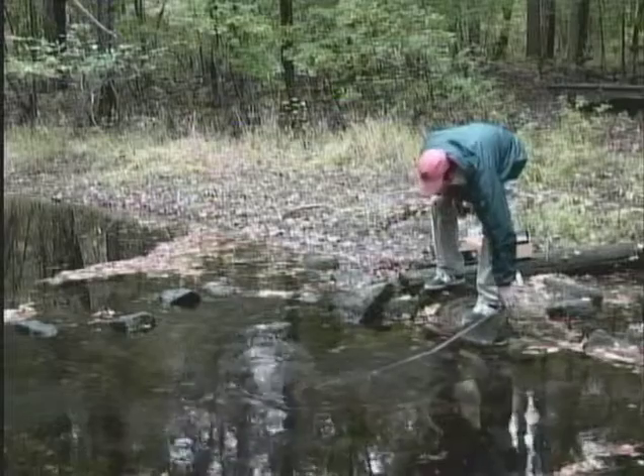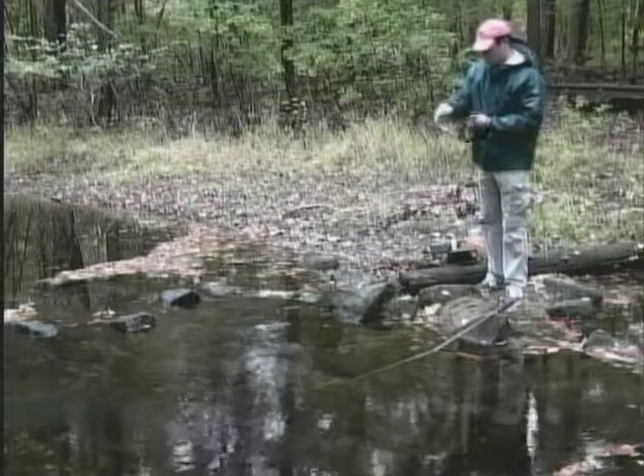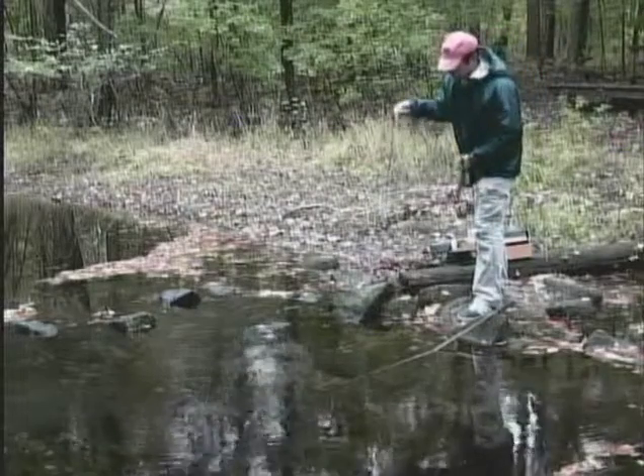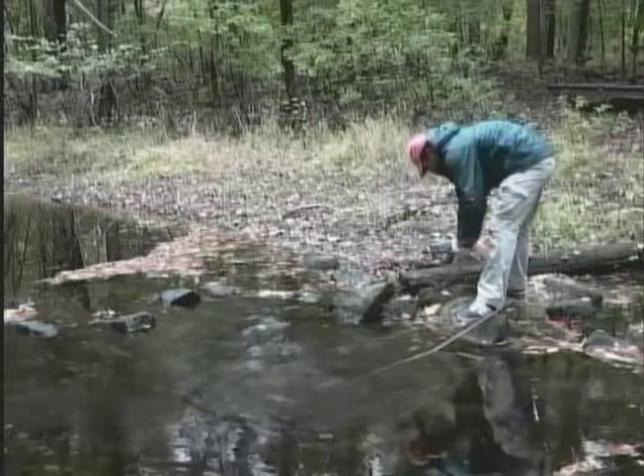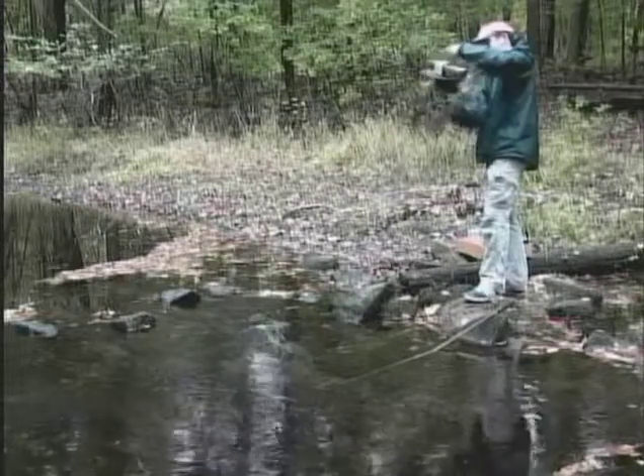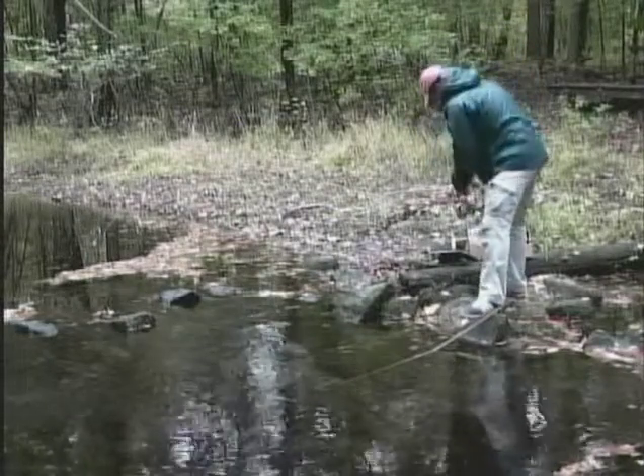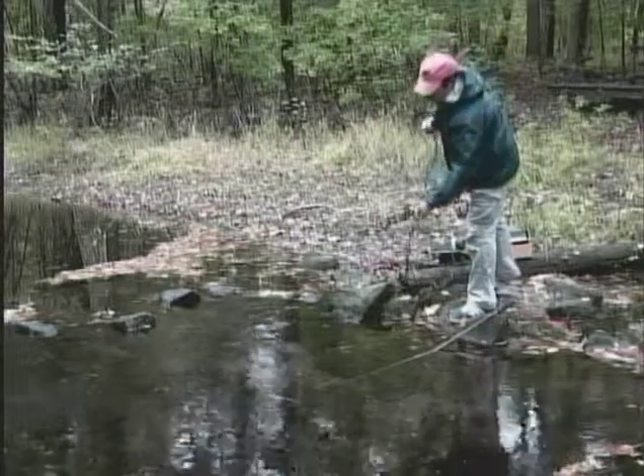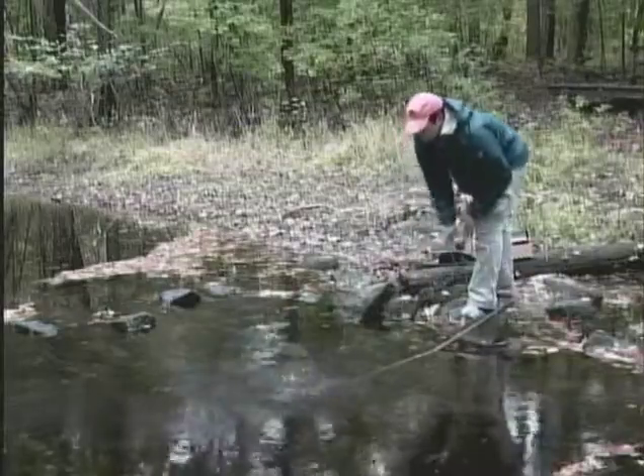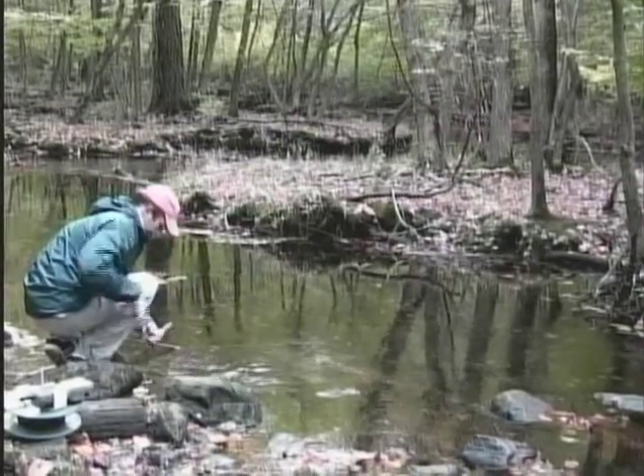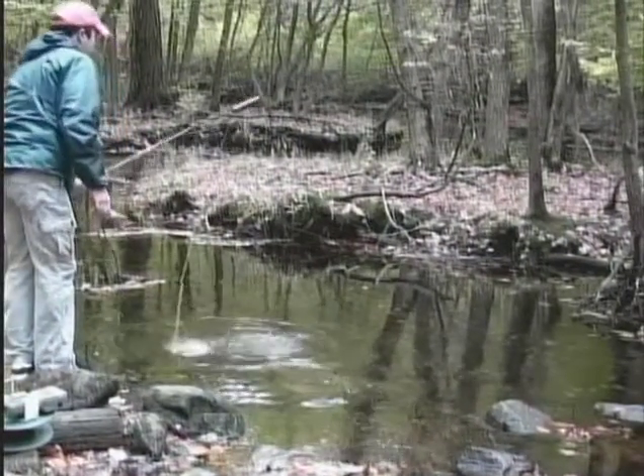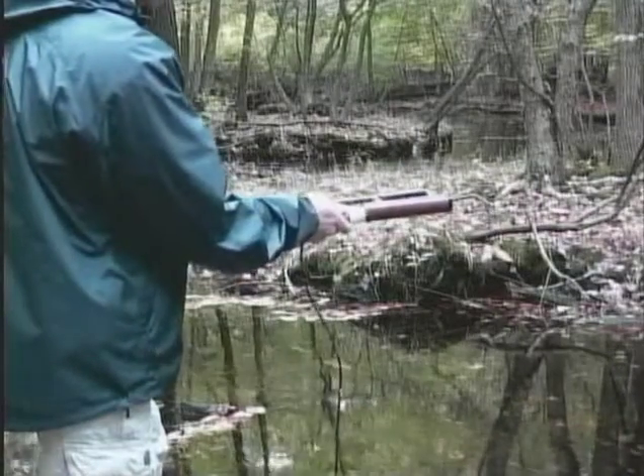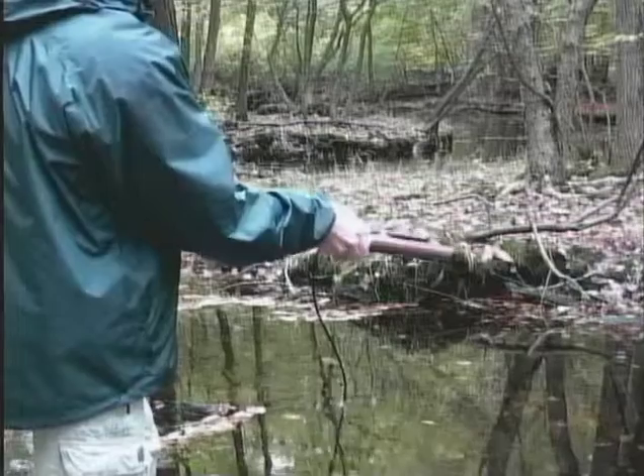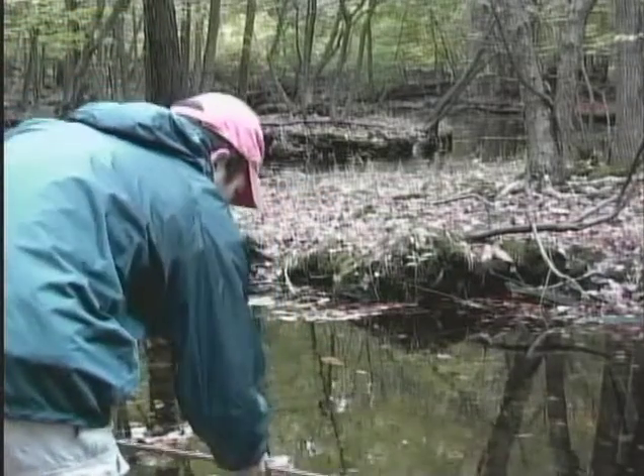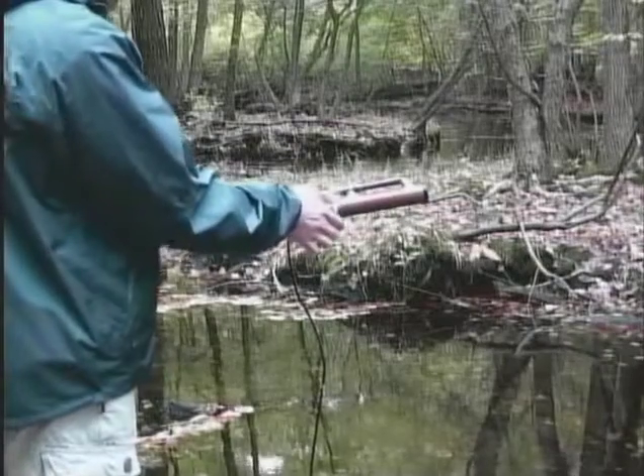Place the calibration wand, DO probe, and conductivity probe into the water. Remember to turn the SCT meter on. After the calibration wand has had sufficient time to cool to the water temperature, and this usually takes about 5 to 7 minutes, take the wand out of the water and pour out the water from the calibration chamber. After doing that, place the probe into the moist chamber. The probe now is in a humidified chamber, more closely attuned to the ambient water temperature that will be tested. Allow about 2 minutes for the probe to equilibrate in the wand.